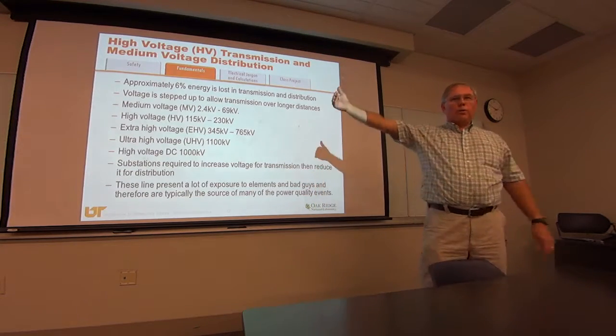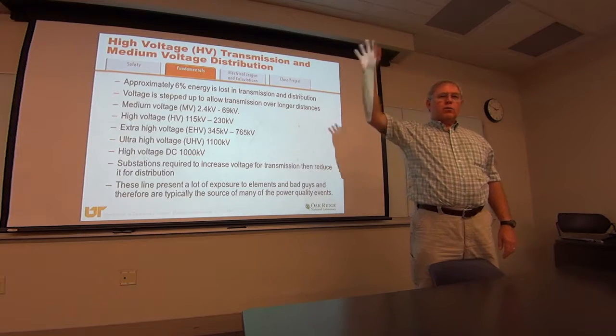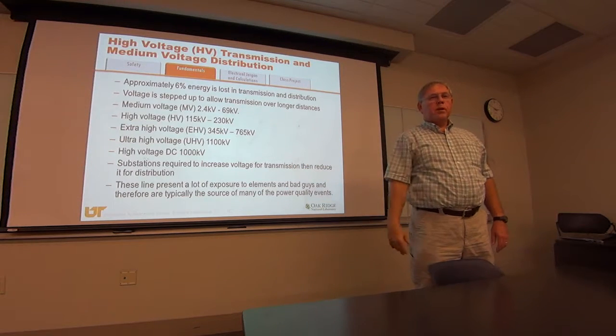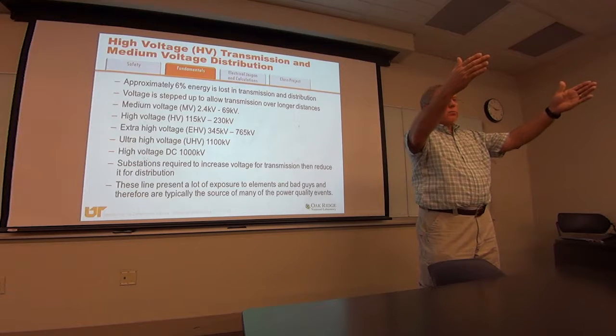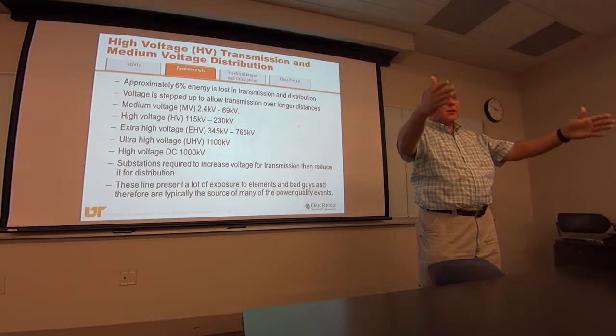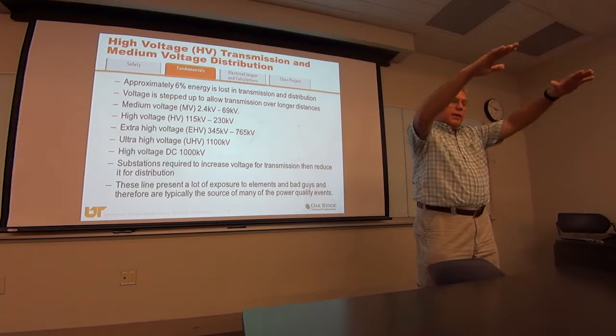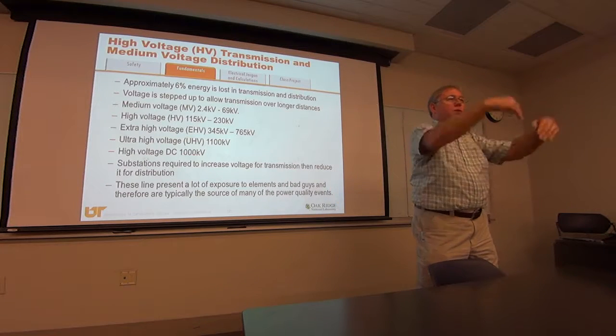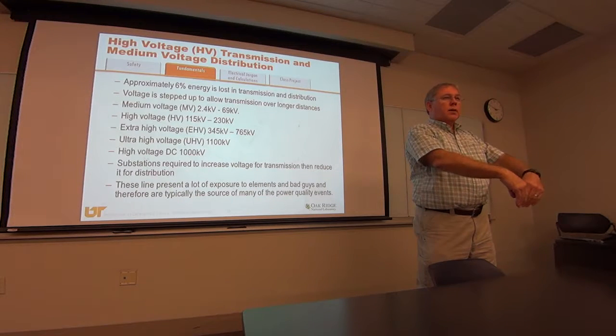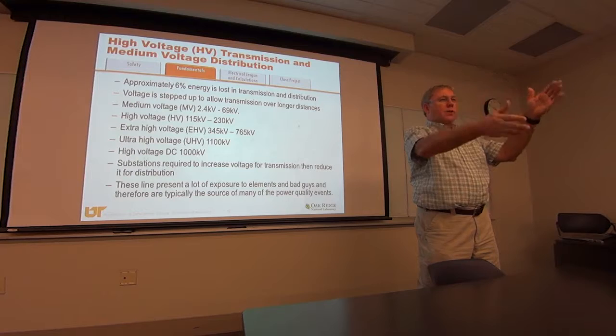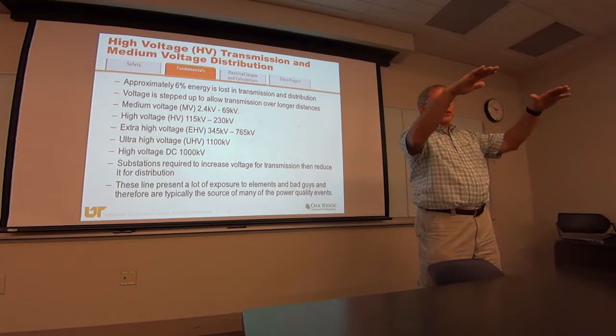TVA would have a fault on a 161 line 10, 20, 30 miles away, and that line would arc for about 5 cycles out of a 60 cycle second. During that time, the voltage would drop because so much current flowed into that fault.